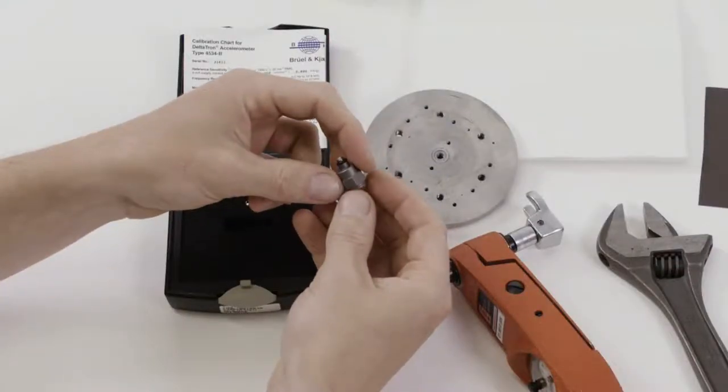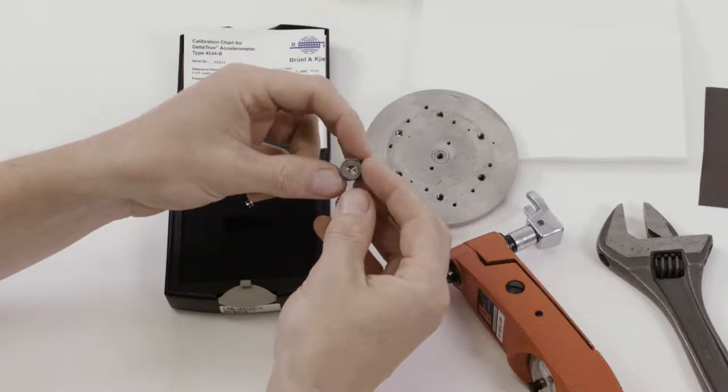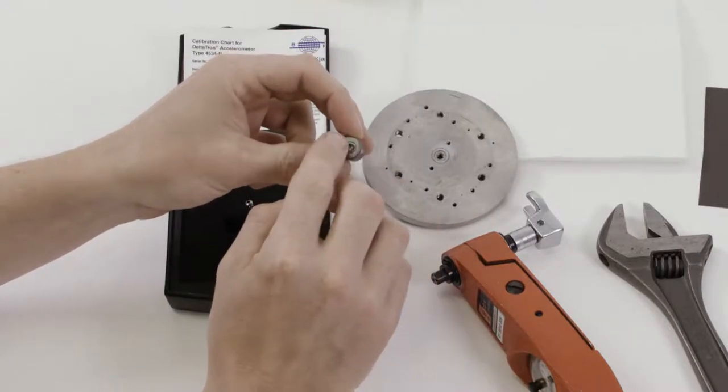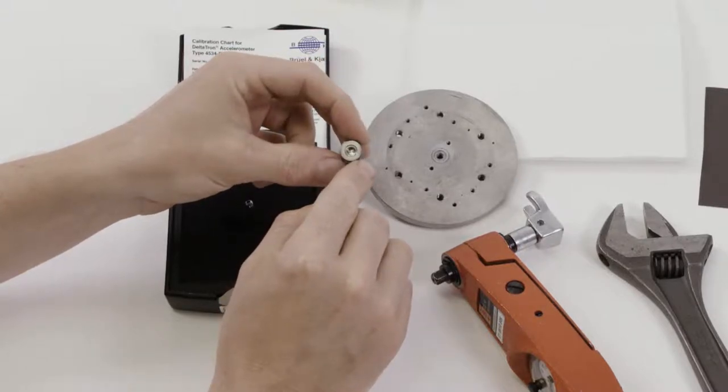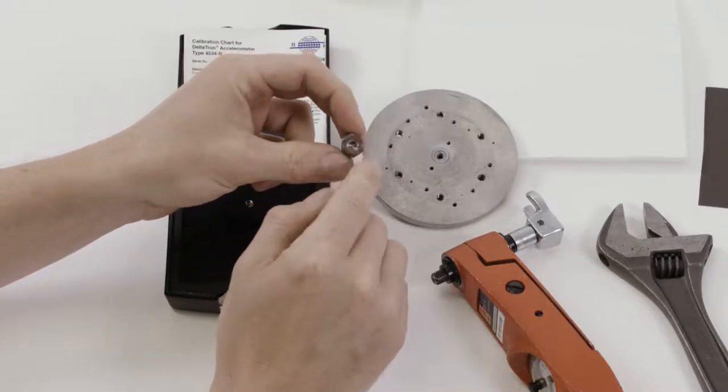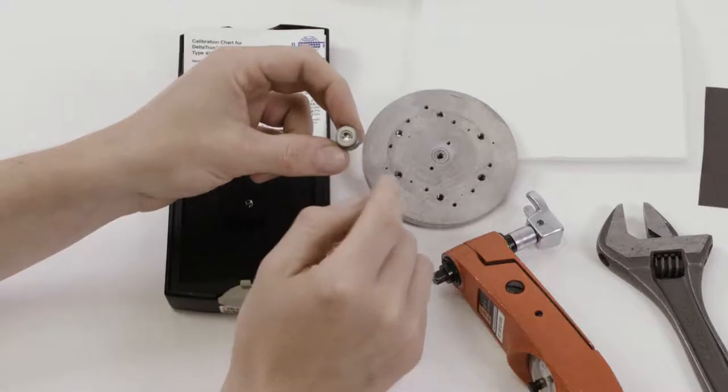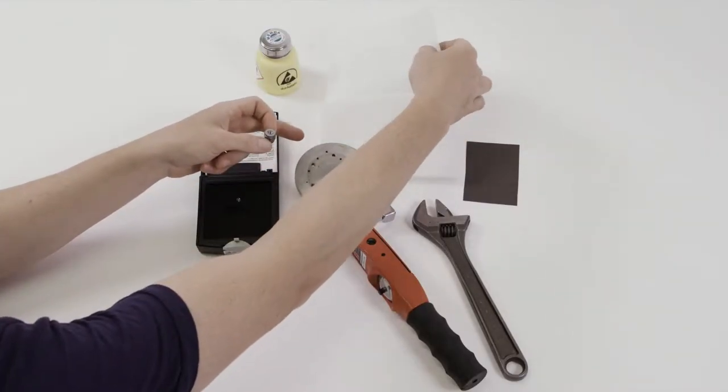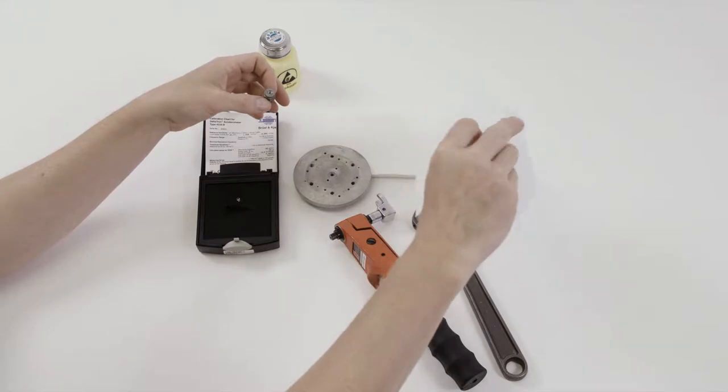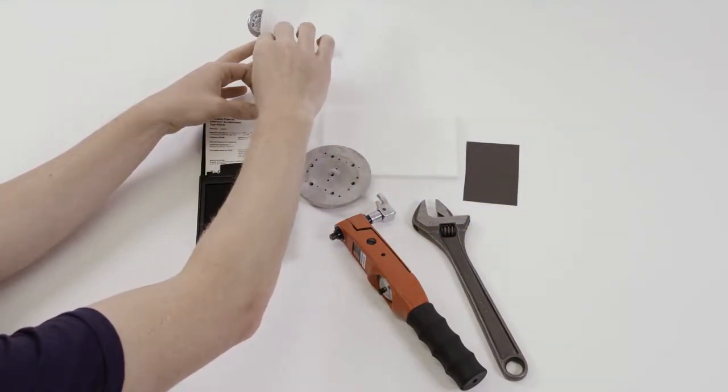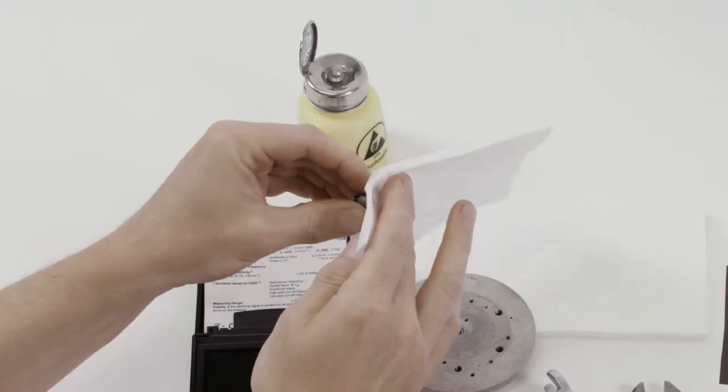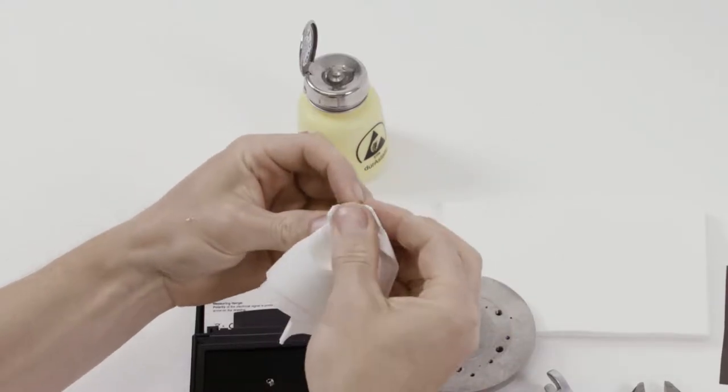Before mounting an accelerometer, always check and inspect the mounting surface for cleanliness and damage. If residues, for example of grease from prior mounting is present, use a cloth or tissue wetted with alcohol to simply clean off the surface.